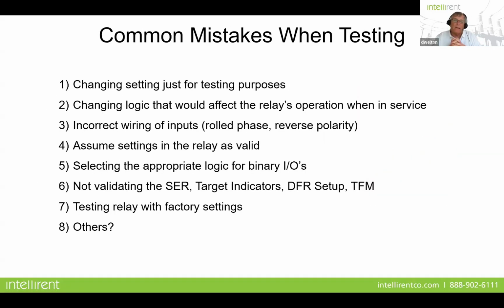So common mistakes when testing, and this is really, I think, pretty important, because I've seen this a lot. And I'll give you an example. We were out at a nuclear facility, doing a commissioning test on a transformer differential element. And when I went to the nameplate and configured, I looked at all my settings, or looked at all my test values that I was putting in, the relay was tripping. And I turned to the utility technician and I said, this thing isn't testing correctly.